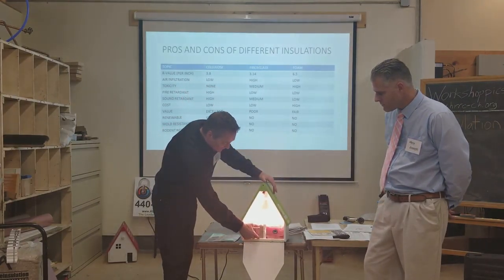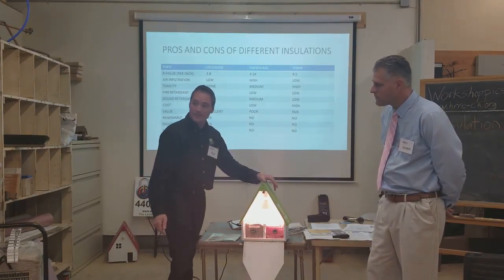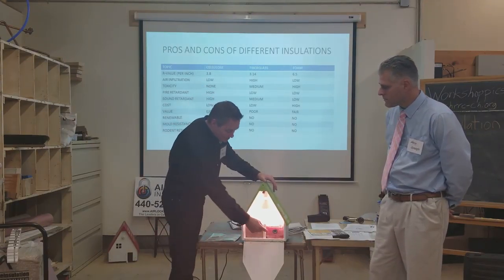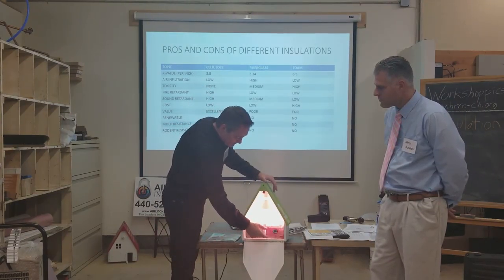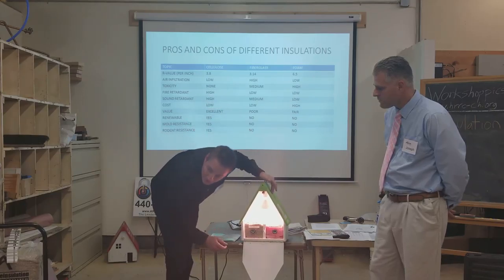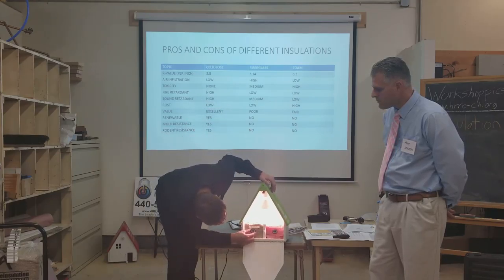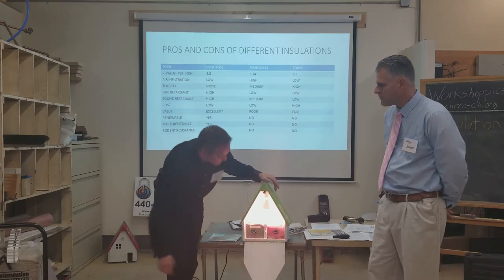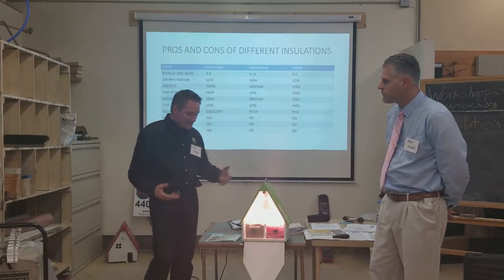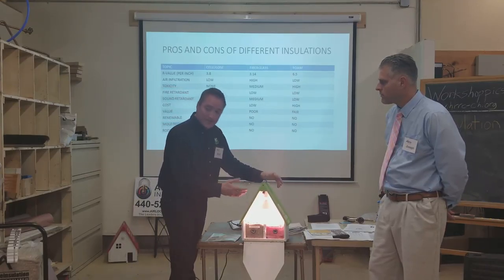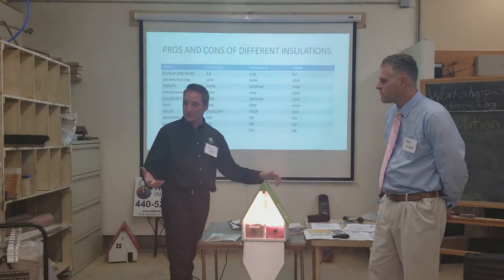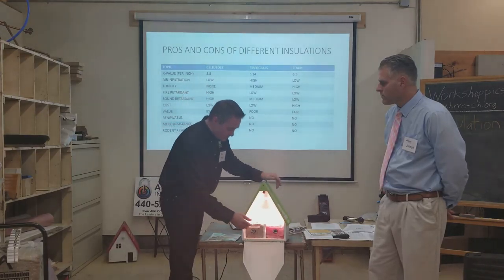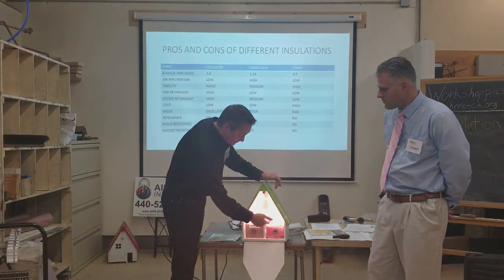At three and a half inches of cellulose you get an R13. At three and a half inches of fiberglass you also get an R13. To give you another set of numbers: cellulose is 67.9 and fiberglass is 75.5. That's how they came up with the concept of R-value — under conduction only. Heat transfer from one side of the surface to the other side.